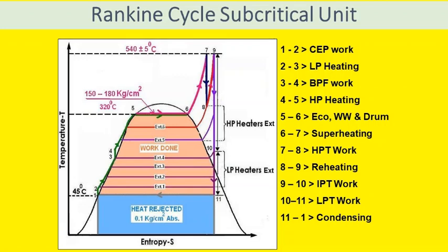So it is the CEP work, and 2 to 3 is part of low pressure regenerative feedwater heating with steam extracted from LP turbines and IP turbine. So LP heating is there between 2 and 3, which is adding heat to the condensate.